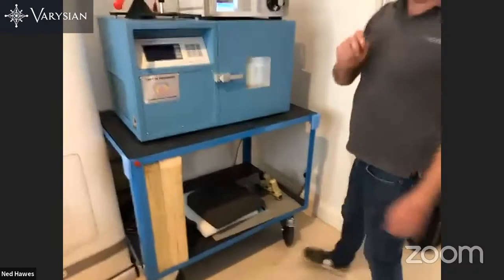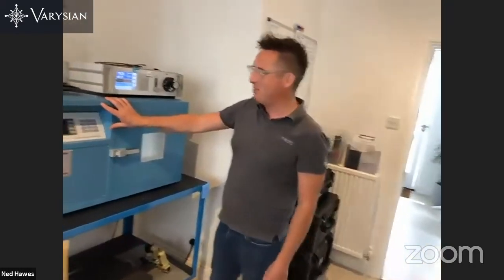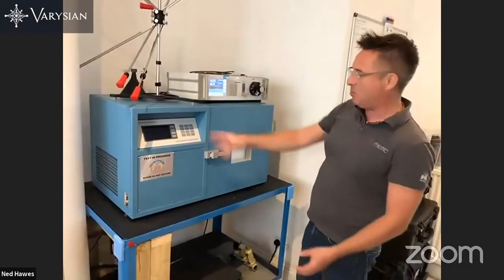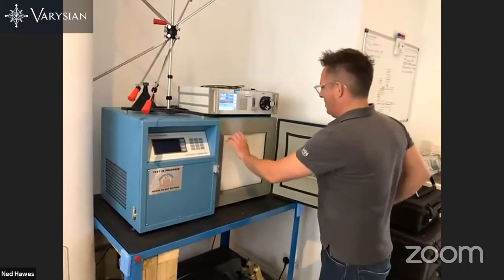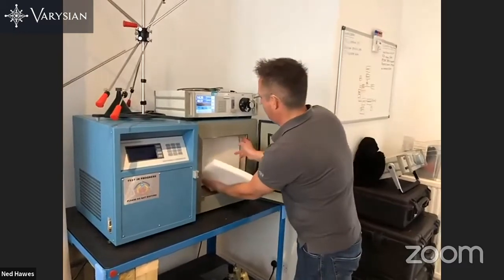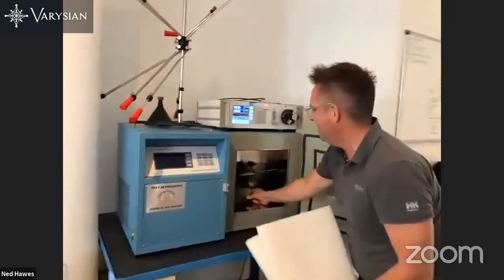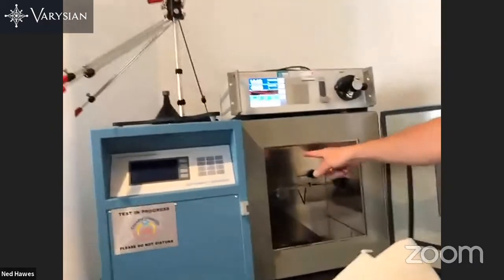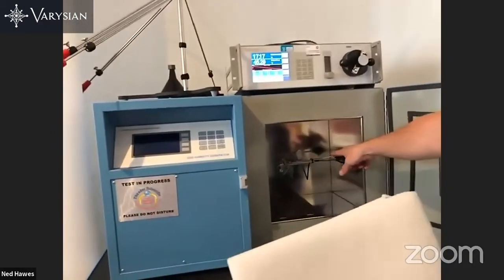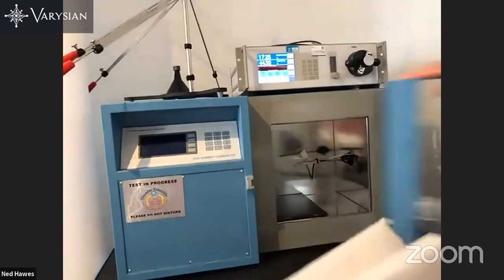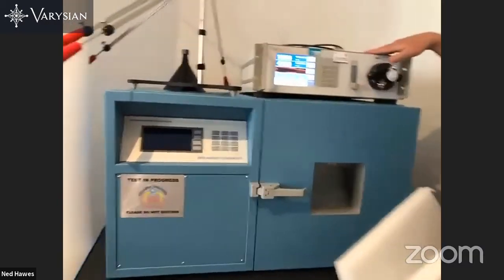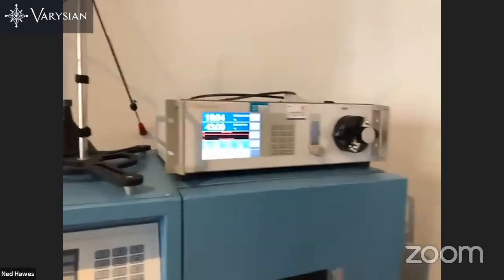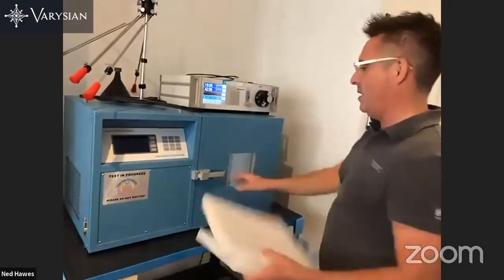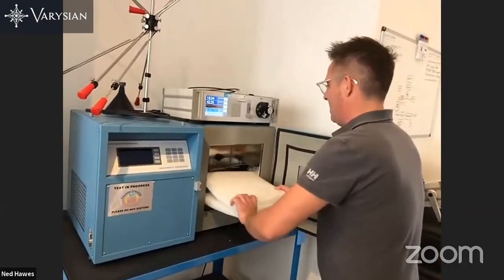And then lastly, we have what's used at the national standard level, which is a Thunder. I haven't got it turned on right now because it's quite loud, so you probably wouldn't hear me talk about it turned on. It uses a compressed air supply and a two pressure system into a chamber here. Within the body we have temperature probes and a humidity generating body, and then we sample out the humidity gas into this external MBW. I'm going to focus on the 473 systems and talk you through exactly how they're set up and how they work.